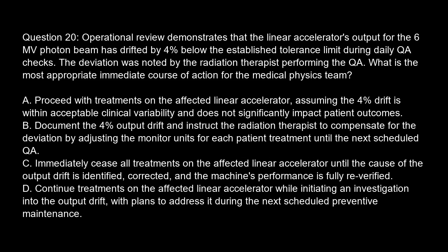Immediately cease all treatments on the affected linear accelerator until the cause of the output drift is identified, corrected, and the machine's performance is fully re-verified. Explanation. Scenario analysis. This scenario presents a common challenge in medical physics where a discrepancy is identified during routine quality assurance (QA) that could impact patient safety and treatment efficacy. The professional challenge lies in determining the appropriate course of action to rectify the issue while adhering to regulatory requirements, maintaining patient care, and ensuring the integrity of the treatment delivery system.